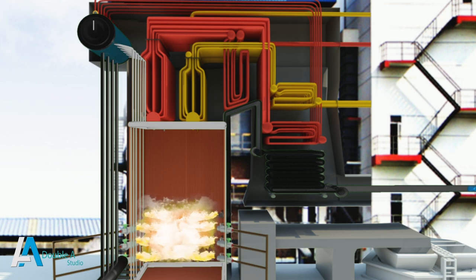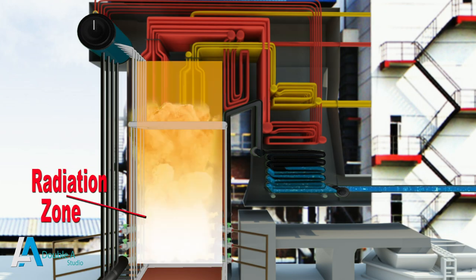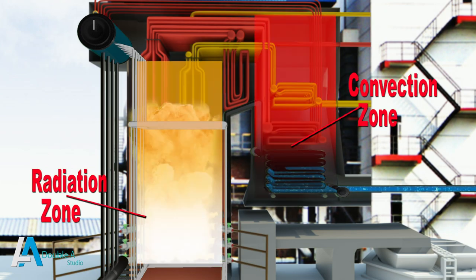Depending on the location and mode of heat transfer, superheaters are classified as radiation type and convection type. Radiation type superheaters are placed in the radiation zone, that is, near the combustion zone, where steam inside the superheater tubes gets heated through direct heat by radiation. A convection superheater is located in the convection zone of the boiler, usually ahead of the economizer, installed in the path of hot flue gases to recover heat by convection mode.